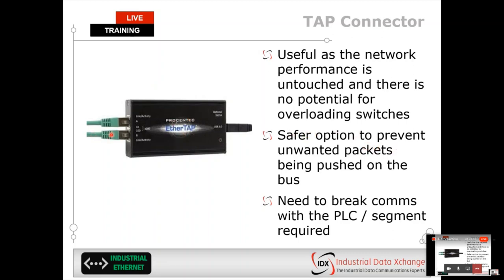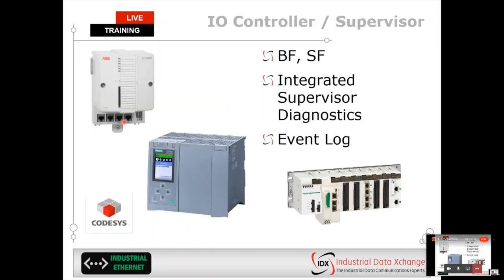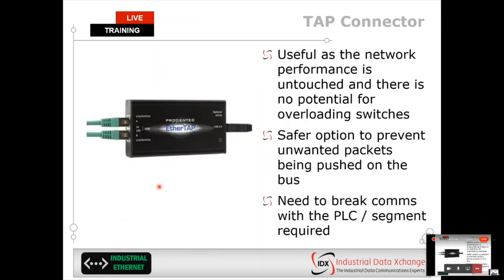This is often a safer option because traffic is only one way - it'll only sniff and listen to data, it cannot send telegrams out onto the industrial communication network. But the challenge with connecting a tap connector is I actually need to break continuity with the PLC in order to plug it in. So to connect it between my controller and the rest of my network, I need to unplug the controller, connect the tap, then plug back in. That might be fine in a breakdown scenario, but when you just want to do a diagnostic health analysis, that can be a bit of a challenge.